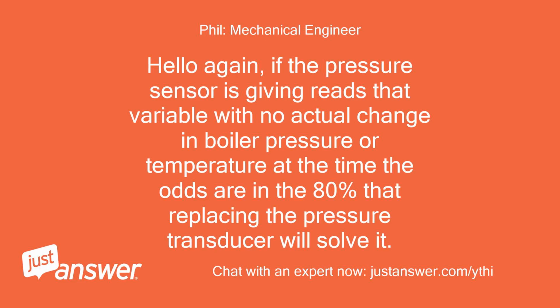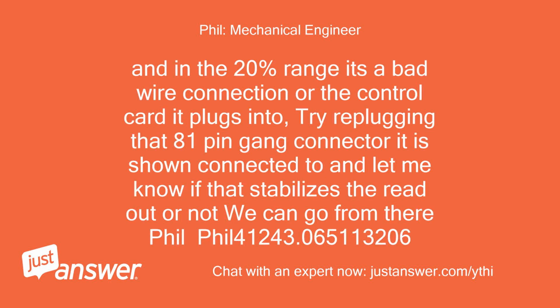Hello again. If the pressure sensor is giving readings that vary with no actual change in boiler pressure or temperature at the time, the odds are 80% that replacing the pressure transducer will solve it. And in the 20% range, it's a bad wire connection or the control card it plugs into. Try replugging that 81-pin gang connector it is shown connected to and let me know if that stabilizes the readout, or not. We can go from there.